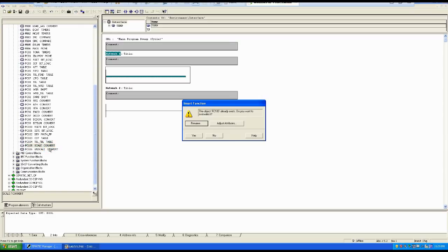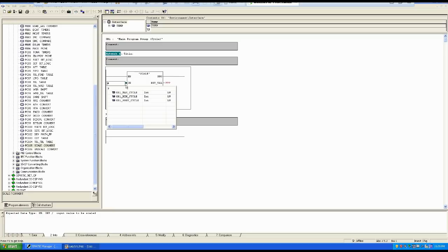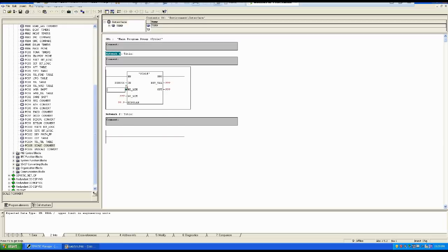Double-click FC105 and it will appear in the programming interface. Remember our address started from 256, so I enter PIW256. After that we define the high and low limits — consider the same example from the last class where we have 0 to 300 level to control. So 0 is our low limit.